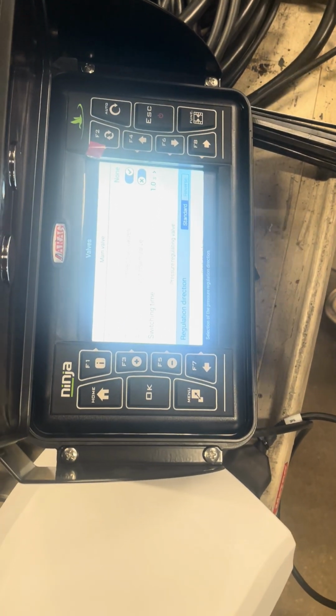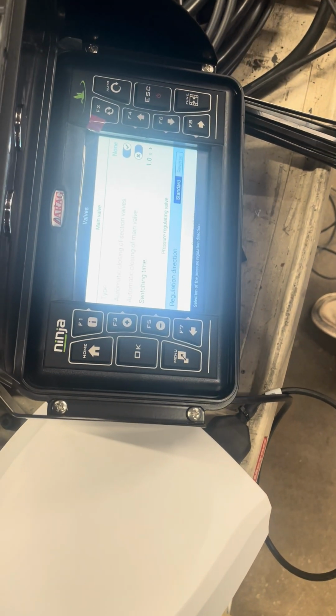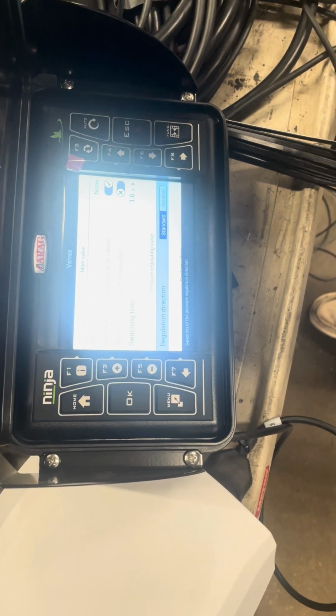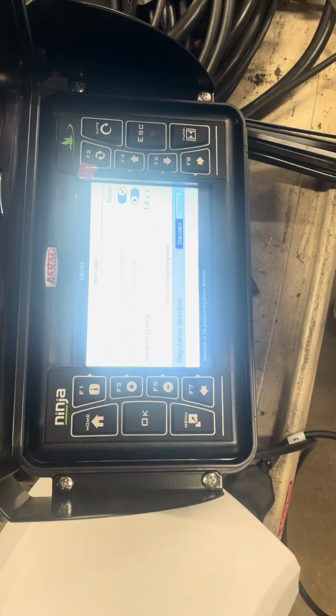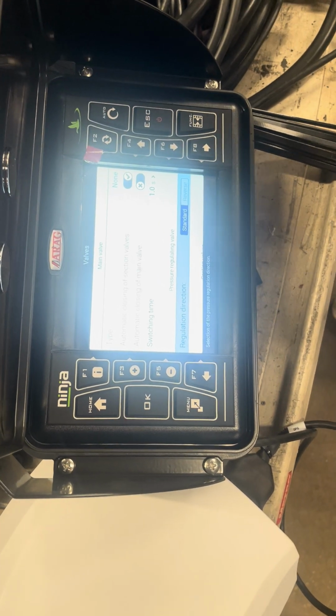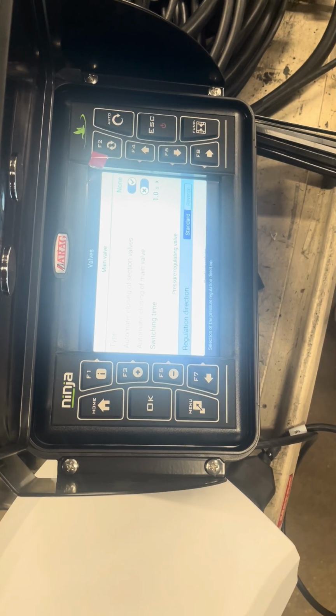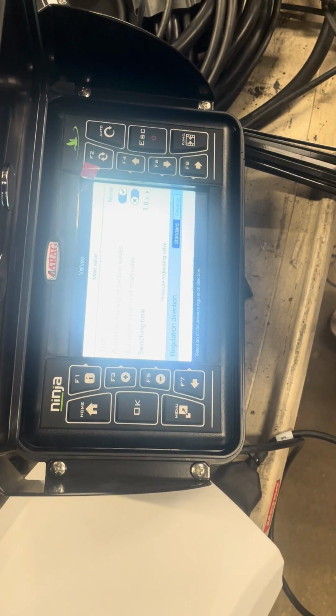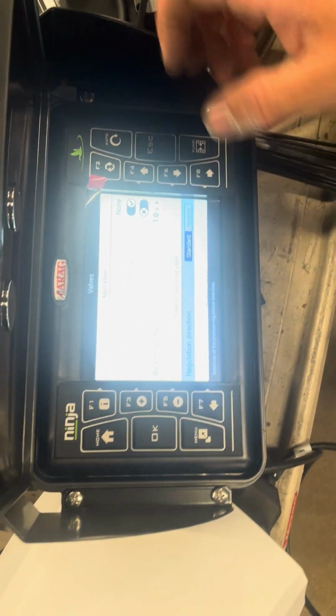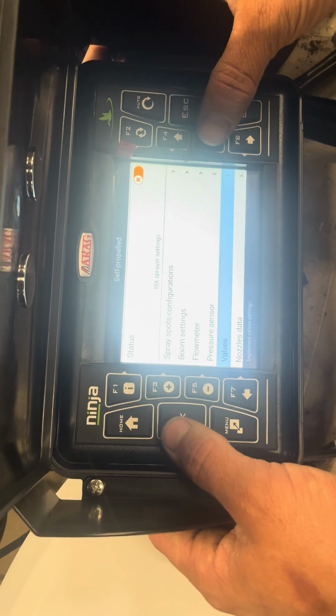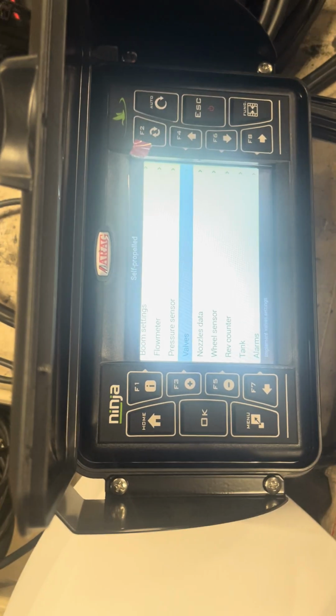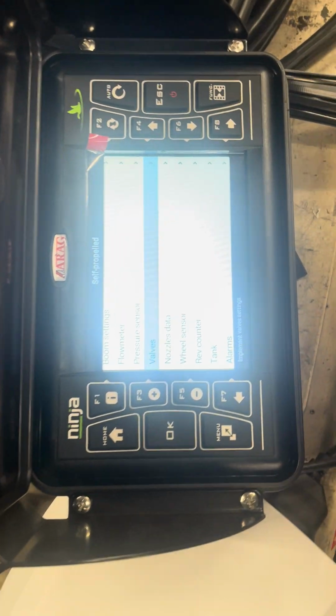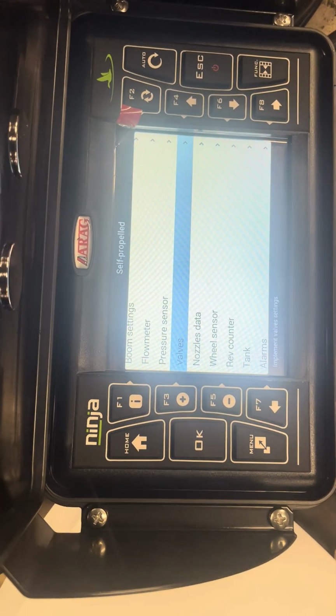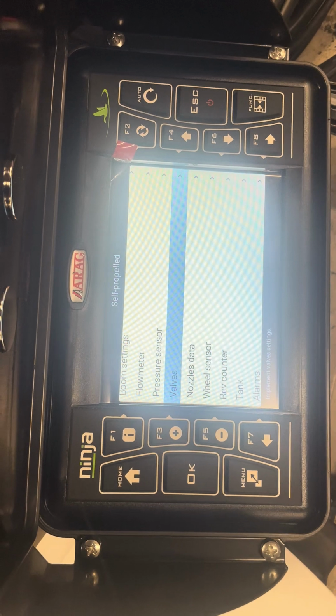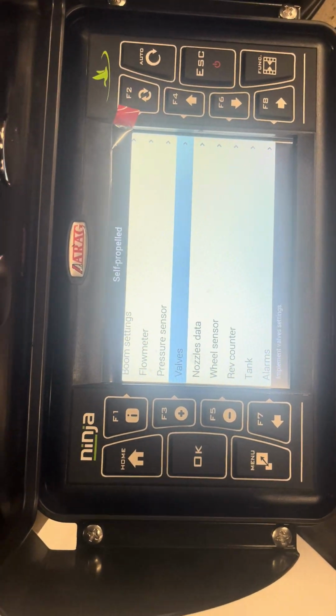Standard. So a good indication is you put the machine in manual mode and run up and down on the joystick and spray, and you'll see the spray get less, spray get more. If it's backwards on the joystick, then you know you have to switch your regulation valve direction. So I'm just going to leave it in standard. But that's when you go out and you lose pressure initially, that's what it is. That's backwards, because it's misreading and saying that it's supposed to be opening, but it's actually closing because the polarity is backwards.